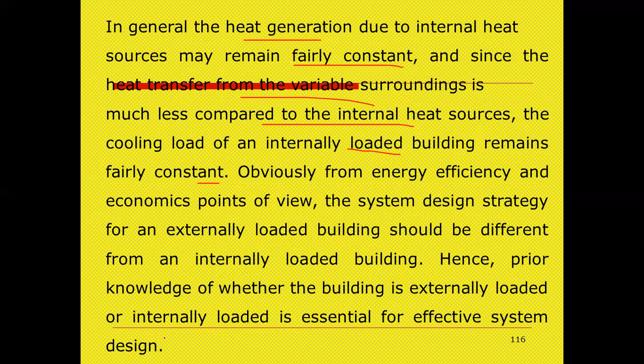So obviously, from energy efficiency and economics points of view, the system design strategy for an externally loaded building should be different from that for an internally loaded building. So the prior knowledge of whether the building is externally loaded or internally loaded is essential for an effective system design. Next, see the simple illustration of a group of occupants inside the room. How many occupants? 1, 2, 3, 4.